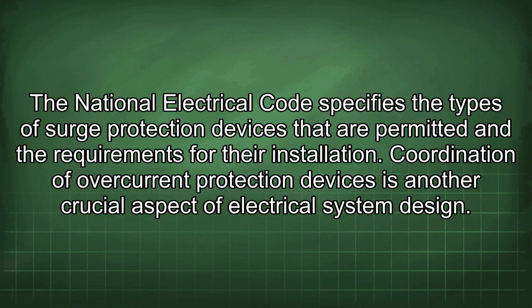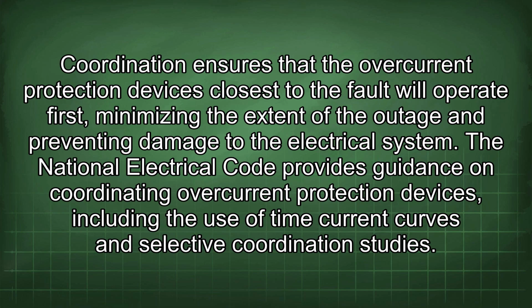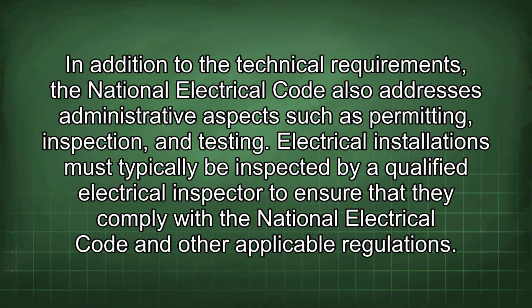Coordination of overcurrent protection devices is another crucial aspect of electrical system design. Coordination ensures that the overcurrent protection devices closest to the fault will operate first, minimizing the extent of the outage and preventing damage to the electrical system. The National Electrical Code provides guidance on coordinating overcurrent protection devices, including the use of time current curves and selective coordination studies.